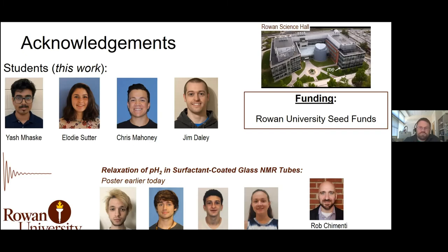That's very wonderful presentation, and I really like your setup. We have a question from Steve here. Can the temperature be maintained for a while, or does it use up the liquid nitrogen quickly? We only ran for an hour and just wanted to keep it consistent for everything. I would say we probably used between a fourth and a third of the liquid nitrogen that we had. It's a 10 liter dewar, and we started with it all the way at the top. I don't know if that rate will change as it gets lower and lower. You might see acceleration or deceleration. I think you could probably go for a couple of hours, but not indefinitely. At some point, it won't work anymore.